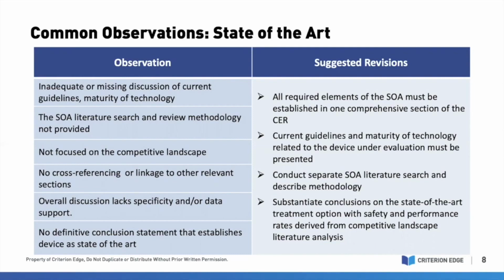Again, try to state your conclusions and then state them again. The notified bodies that are reading these, those folks are likely tired. They've written a lot. They've read a lot. They may be skimming. So if you stated it somewhere, state it again, that you've come to a certain conclusion, that your device is state-of-the-art, that your device is equivalent, whatever the conclusion statements are, it doesn't hurt to repeat yourself.